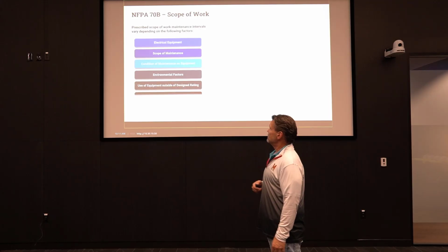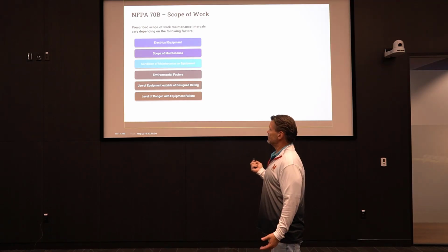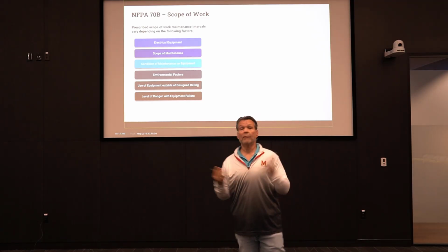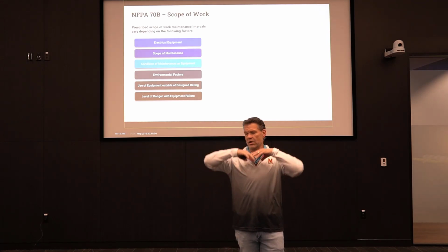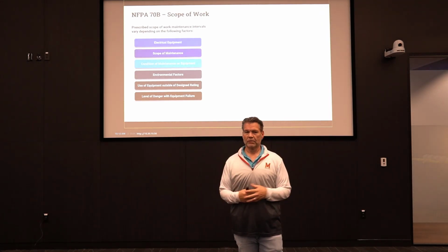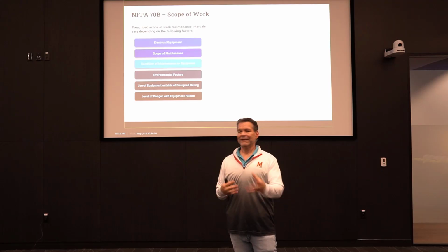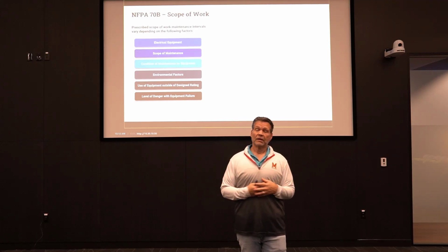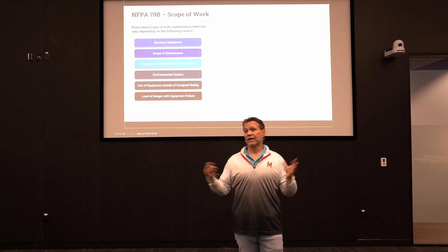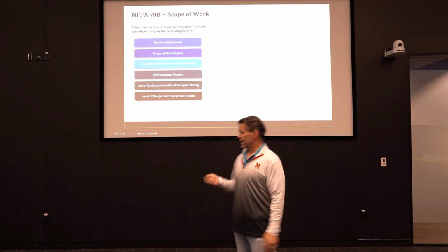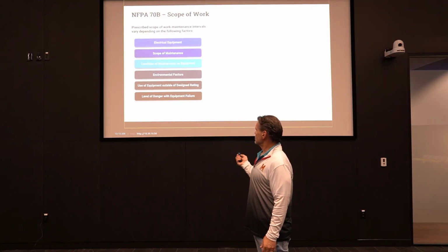So NFPA 70B, scope of work, electrical equipment, scope of maintenance, condition of maintenance, environmental factors. Are we in a sawmill where there is all kinds of sawdust everywhere all the time? That may need to be cleaned and maintained on an earlier basis than equipment that's not in an environment like that. Use of equipment outside of its designated rating, level of danger with equipment failure.